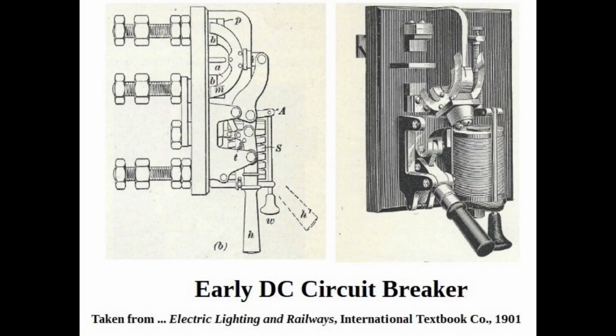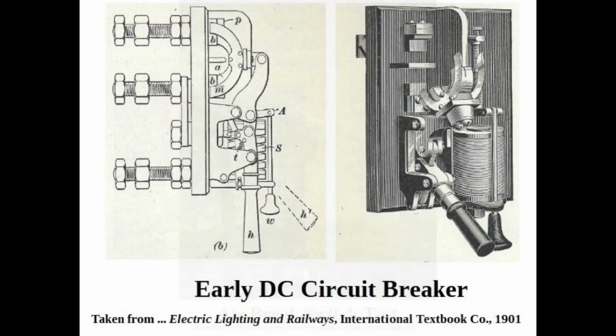Circuit breakers were mostly used for high-powered circuits. If properly applied, they could be reused after clearing a fault. But these were basically glorified switches. In these early days, they didn't need to be much more. In general, direct current arcs could be extinguished by drawing the arc out sufficiently. However, these devices were sometimes destroyed by the current they were attempting to interrupt.